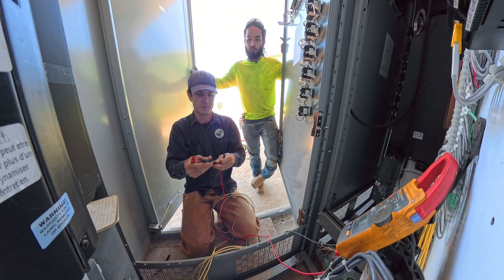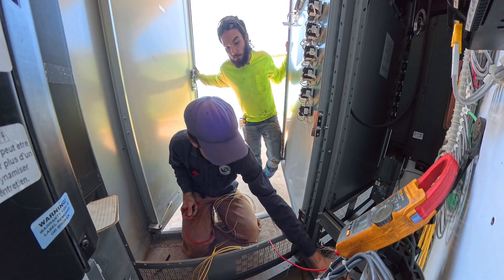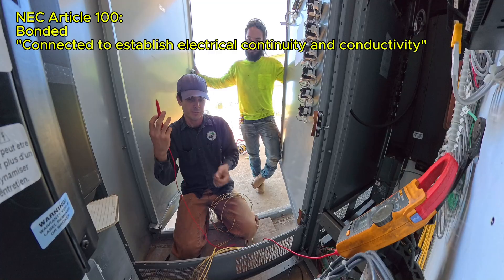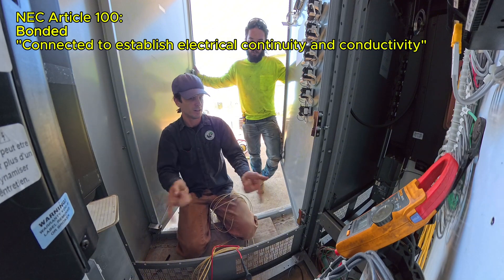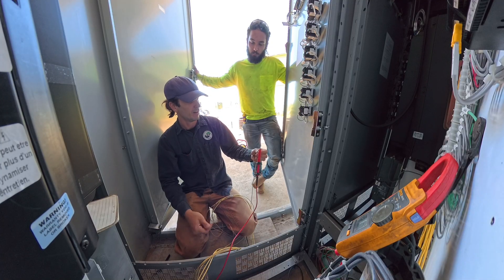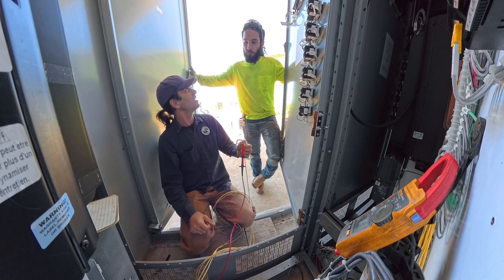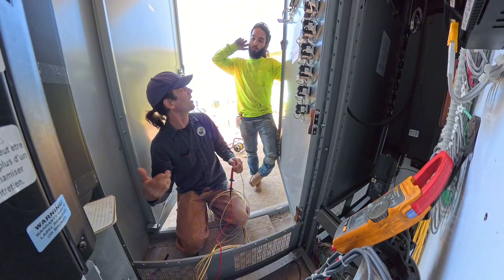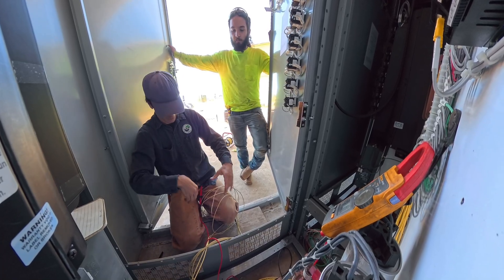We're gonna put one of our leads onto any bare metal, because everything here is bonded so well, and then put the other lead on a wire. If this lead touches bare metal it beeps — it's continuous, it's touching. So you're gonna pick a wire, put this on there, I'll go to the other end and touch those wires to bare metal until you say that's it. Then I'll say let's make it — P3 MCC 116 or whatever — and you slip the labels on. After you slip them on, give a little bend so the label doesn't fall off, and we'll run through all five.